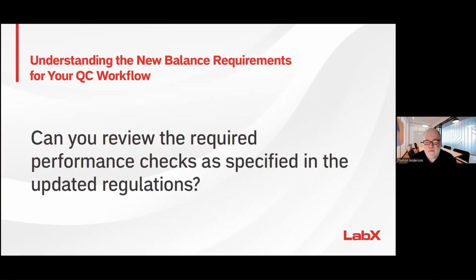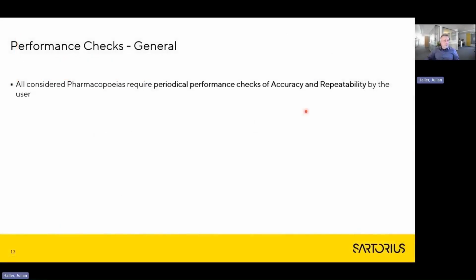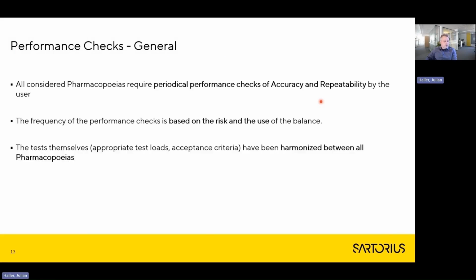Can you review the required performance checks as specified in the updated regulations? All considered pharmacopoeias require periodical performance checks of accuracy and repeatability by the user. The frequency of the checks shall be based on the risk and the use of the balance. And fortunately, the tests themselves, concerning the test loads and the acceptance criteria, have finally been harmonized over all pharmacopoeias.